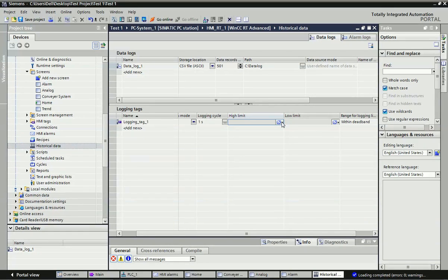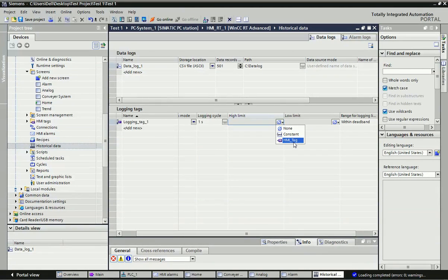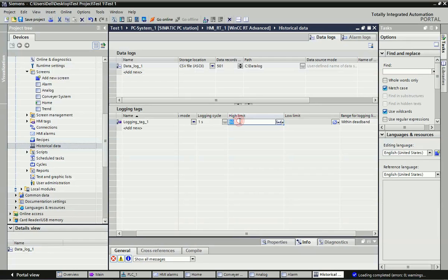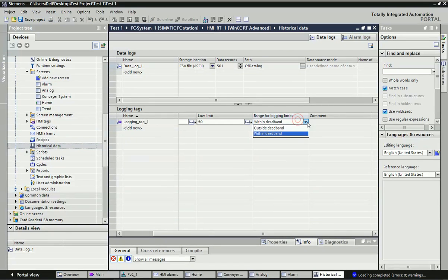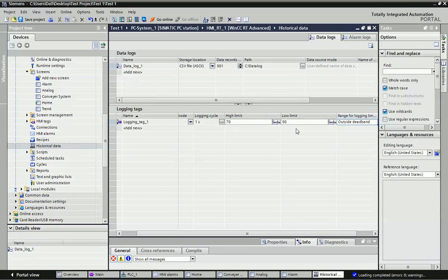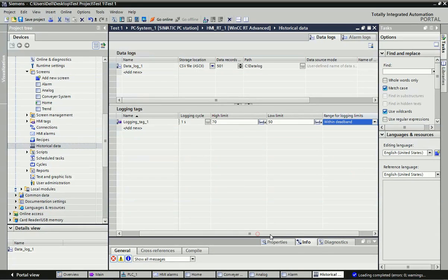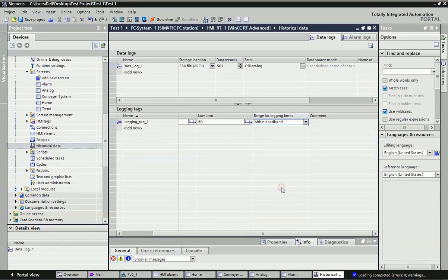Here is the high limit and low limit. Since the analog signal is continuously coming, you can store the data within a limit — within a deadband or outside a deadband. I will make it constant. If you want to change the limit from the SCADA or HMI screen, you can go for an HMI tag. I will assign the low limit as 50 and the high limit as 70. Here you can also set the deadband — if you select outside deadband, this data will be stored outside the 50 and 70 value limits. I will select within a 10-unit deadband. You can also add a comment here if you want.